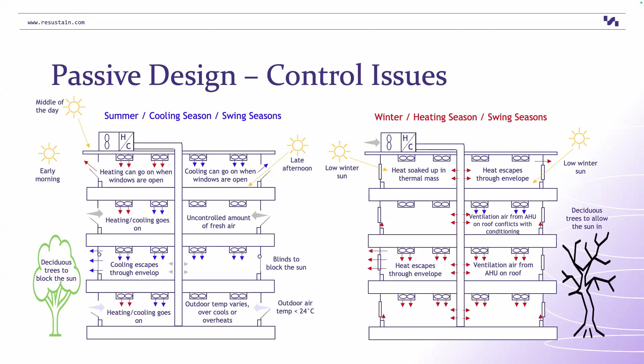You've got a thin envelope, which is great for bringing heat in, but not great for holding it. Also not great for holding the cool, so the cool escapes as well. So unless you control the envelope and the windows very carefully, you have potentially a lot of conflicts with that and the energy usage within the building. In the heating season, similar things happen. You can potentially have ventilation air coming in too warm, which triggers the cooling in the winter. So you get conflicts, and also your light envelope allows the heat to escape. So it has a lot of benefits, but it also has some control issues, which make it very hard to make sure we're using it correctly in the swing seasons.